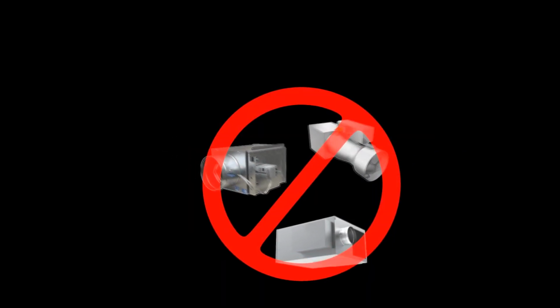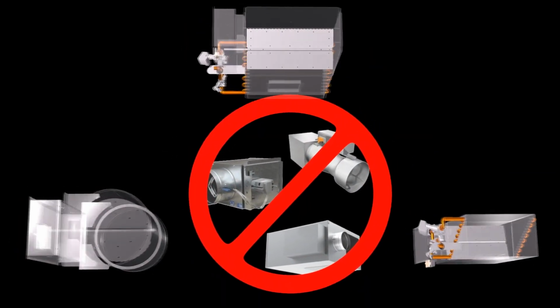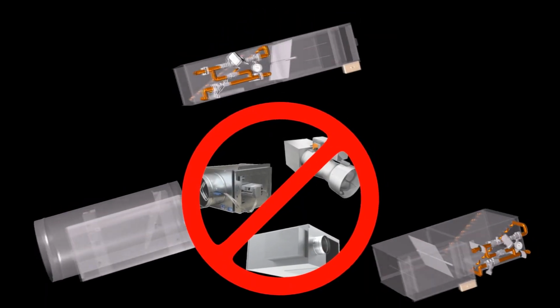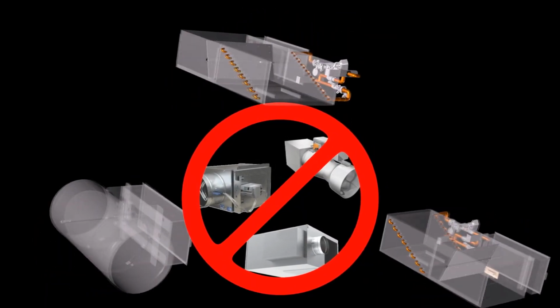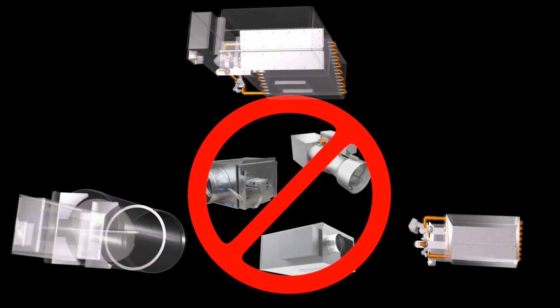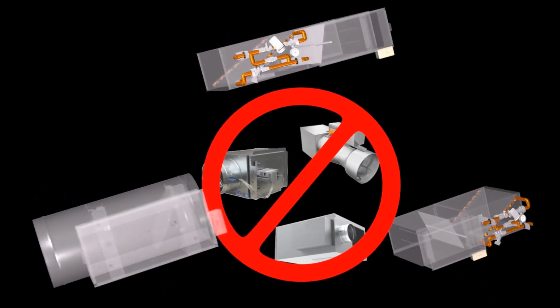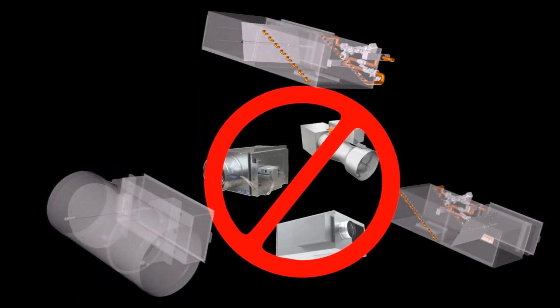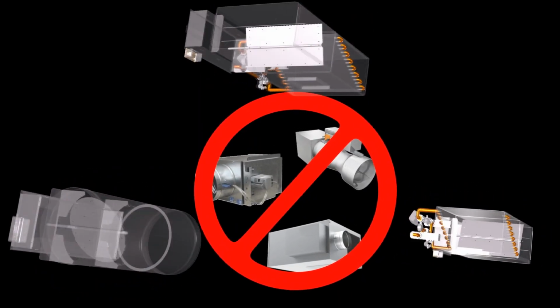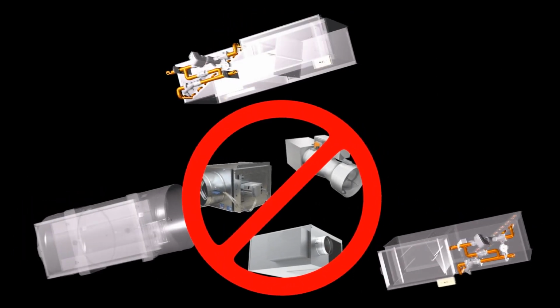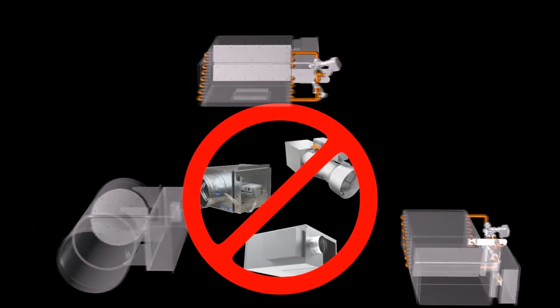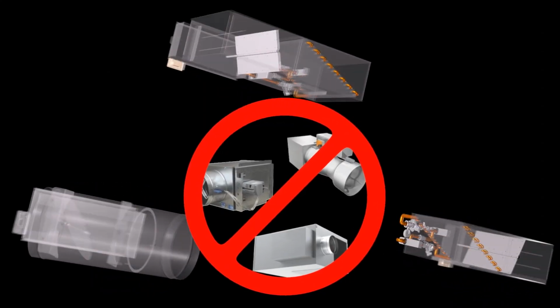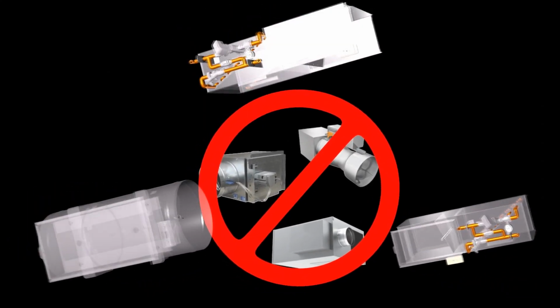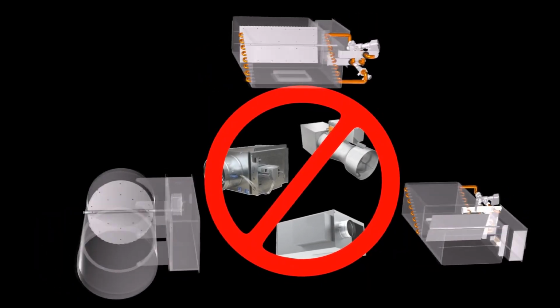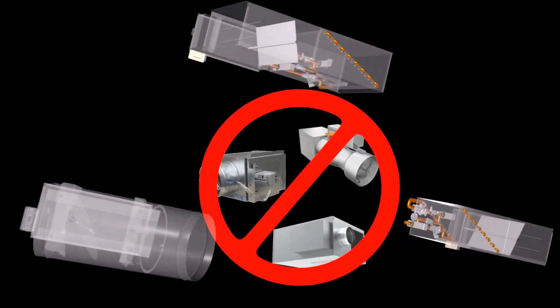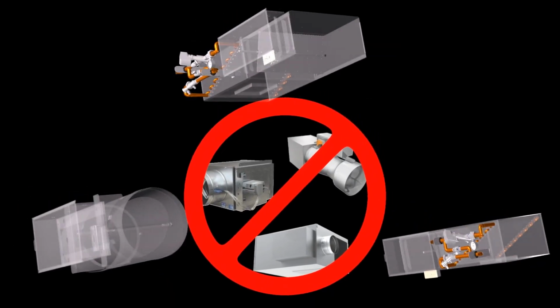The patented VOPT, variable orifice plate technology flow measurement obsoletes fixed orifice air terminals. VOPT transforms the damper into an intelligent aperture, which is an all-inclusive variable pressure magnification, flow measurement, and flow control device. The pressure magnification is over 100 times at low flows. The physics of the pressure measurement magnification works inverse of fixed orifice air terminals, and therefore the transducer will not bottom out at low flows, allowing for the damper to be calibrated over the entire dynamic range on highly accurate flow stands.